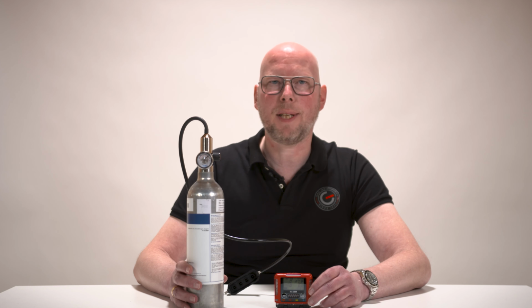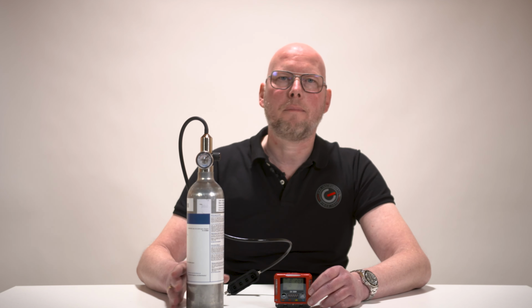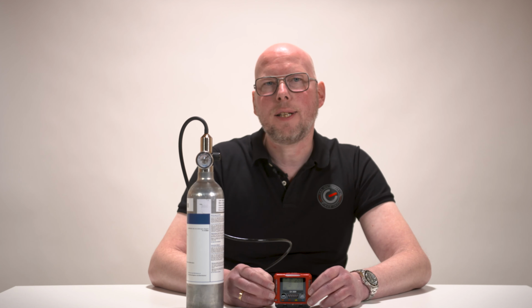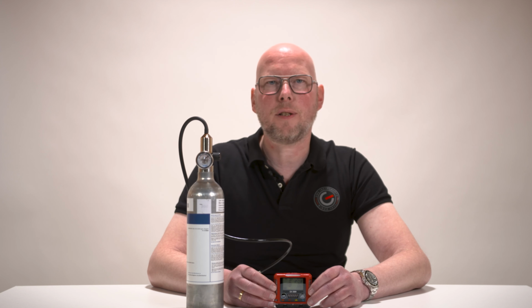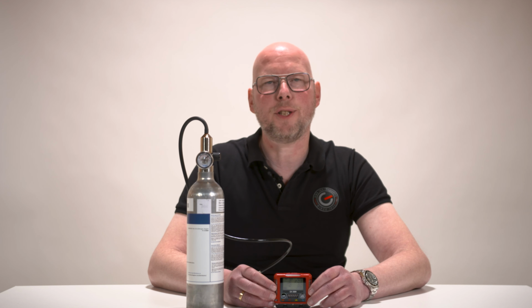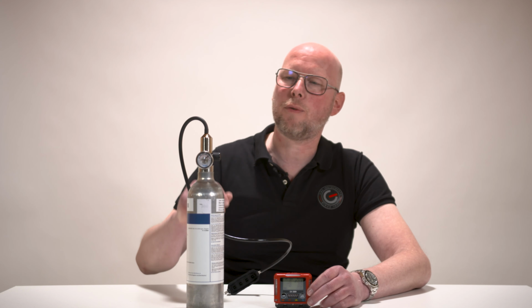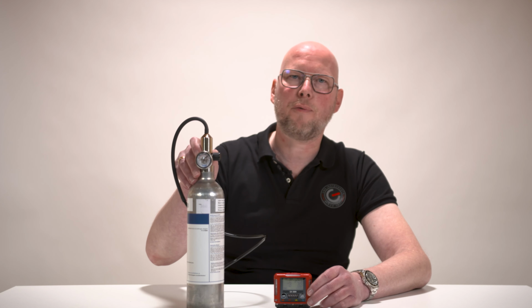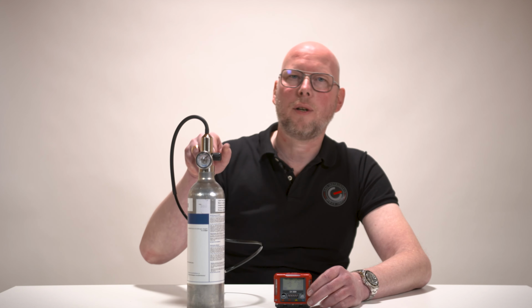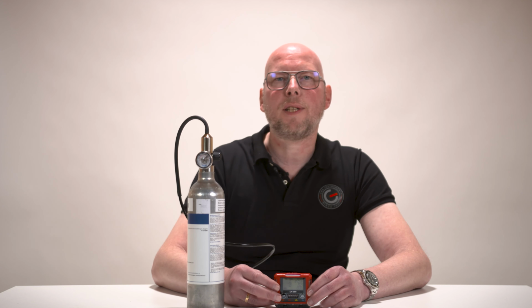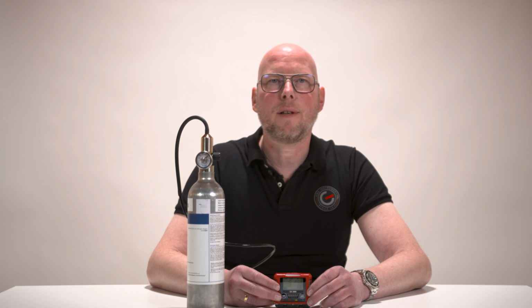contains 50 ppm CO, 25 ppm H2S, 2.5% CH4 and 12% O2. Model GX-2009 is a gas detector without internal pump, so-called diffusion type. Therefore, the regulator we use for model GX-2009 is the fixed flow regulator with 0.5 liters per minute flow rate.